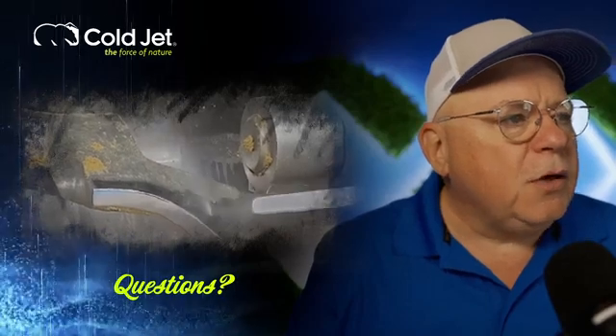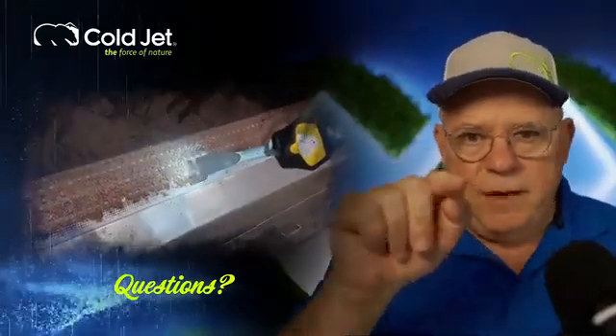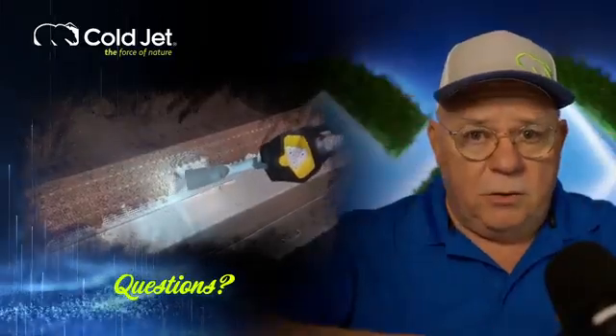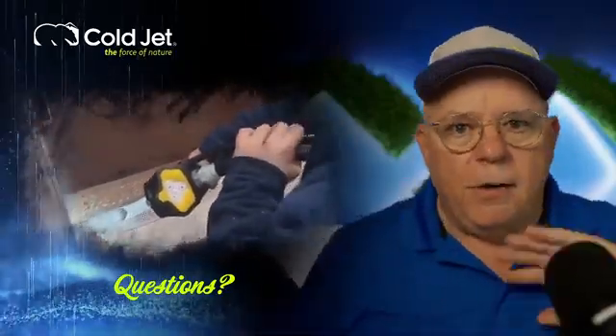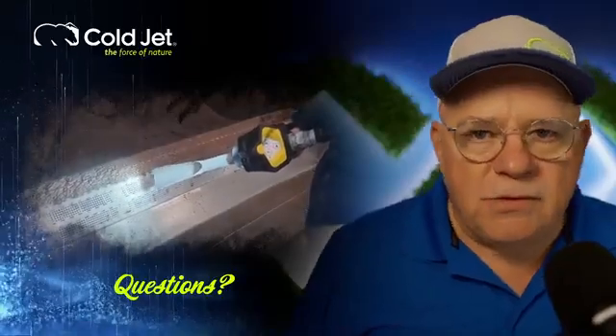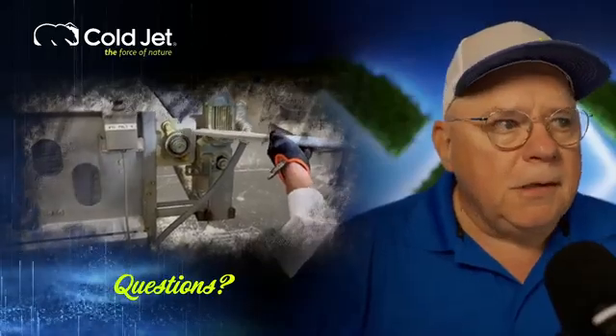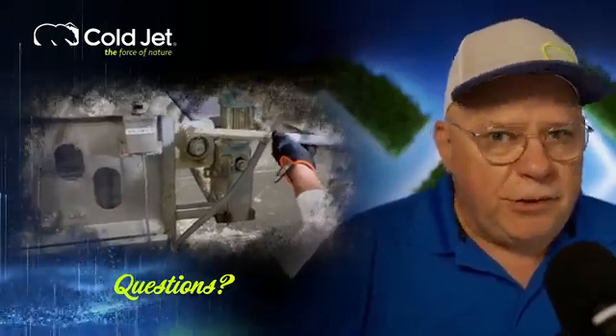The next question is risk of suffocation. Well, yes. The way dry ice and CO2 work, when you force the sublimation of that pellet, the CO2 goes down to the floor, out to the wall, and up to your nose. If you're in a confined space, yes, you have to make up that air. You have to exhaust it and make it up. Now, if you're out in a 50,000 square foot plant, it's just going to find its way out a dock door. So yes, you have to lock out a pit if you have a pit. You have to understand CO2, and we can train you on all of that.